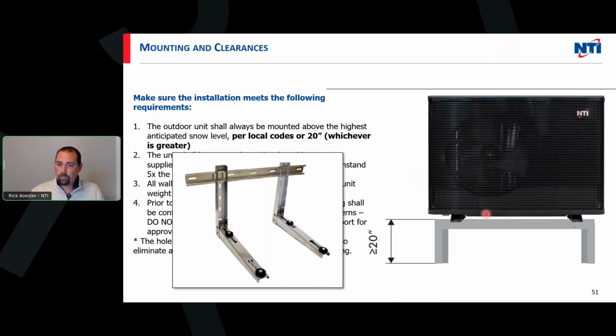The other thing is noise. I've never been a huge fan of wall brackets, just because when you have a machine, any type of mechanical device, on a metal bracket that's now bolted into a wood structure, you're going to hear some sort of harmonic or vibration coming through there. If there are no vibration eliminators on here, you're going to have some kind of noise that may be a complaint. So I try to avoid it. And for whatever reason, it seems every time the contractor puts one of these on a wall, it ends up being a bedroom wall or something like that, or very thin construction. So these things have to be thought about beforehand.